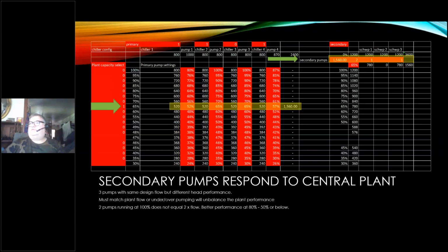And in this case, the 2 pumps running on the secondary at 100% did not equal 2 times the flow. They actually were fighting each other. And so when the second pump came on, the resistance to flow increased. Better performance was 80 to 50% or below. Now, again, when I said 40%, that's when the determination to shut it off would come in. But this chart is what we're trying to automate into this plant.